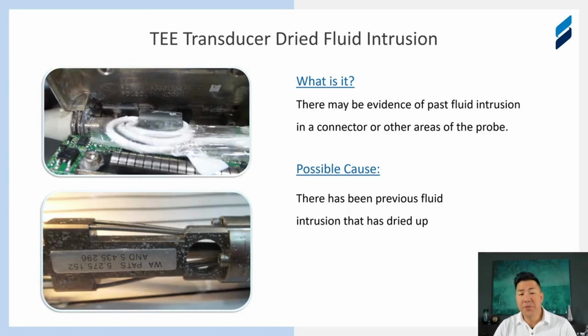Now what happens if the fluid intrusion sits around for a while? The probe might be fine, and you can get lucky. The top picture is of the connector of the transducer where fluid got in, dried up a little bit, and really didn't cause any catastrophic damage, which is fantastic. And the other is the handle here in the bottom photo, and you can see the pitting that has occurred over time because of that fluid ingress, just eating away at that metal.